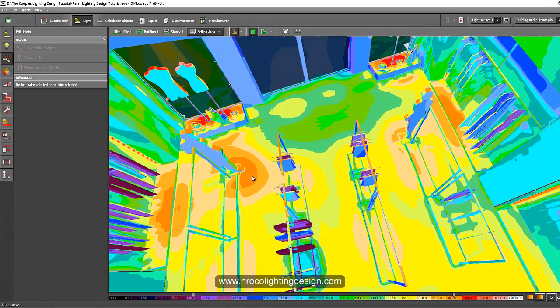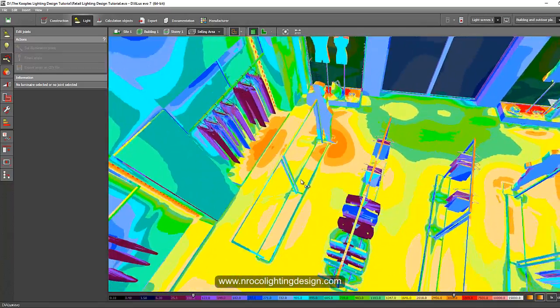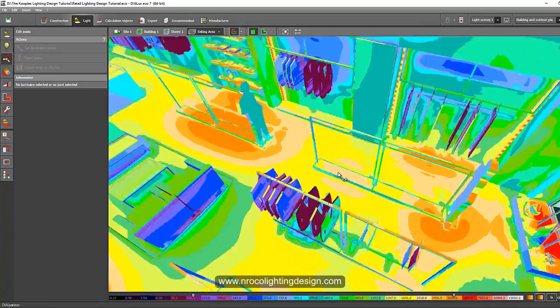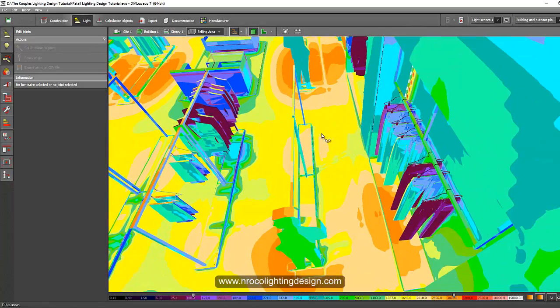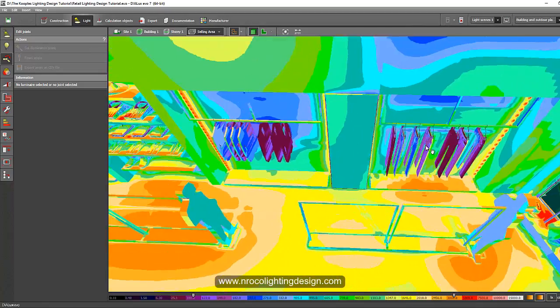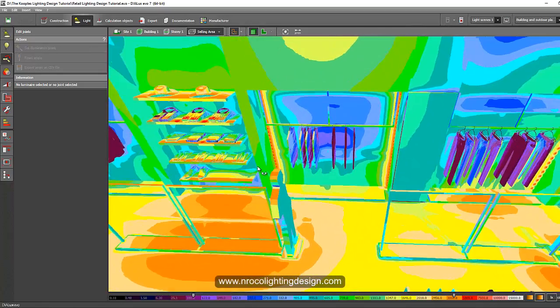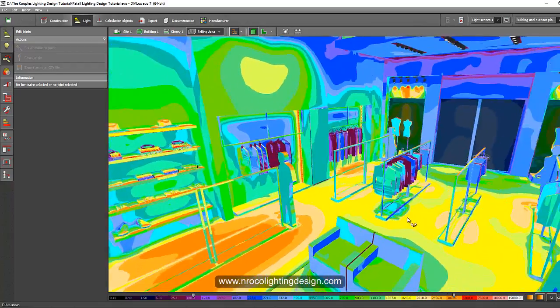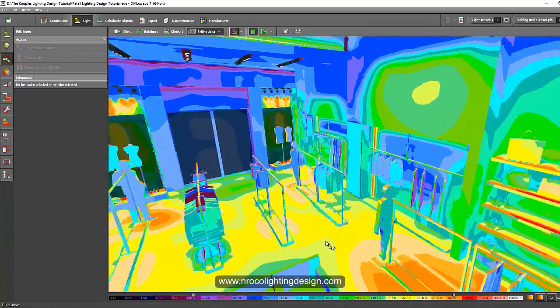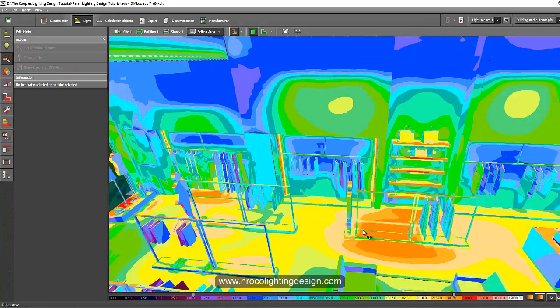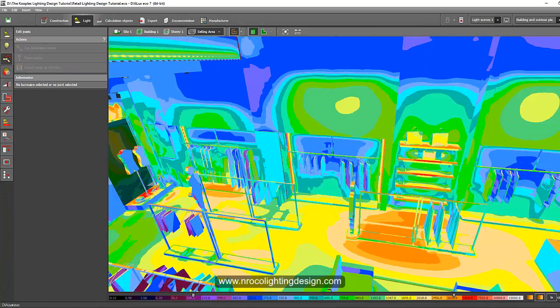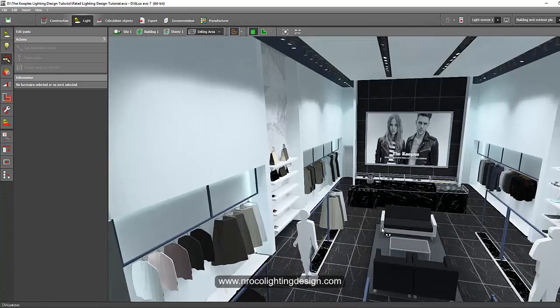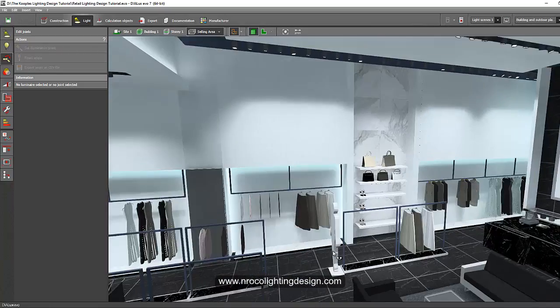On the mannequins you can see the orange — it seems too much. Because of the 3000K color, I think I need to reduce the lumen output of the luminaire. I need to select a lower output or reduce the number of fittings. Let's go and check it in the rendering.